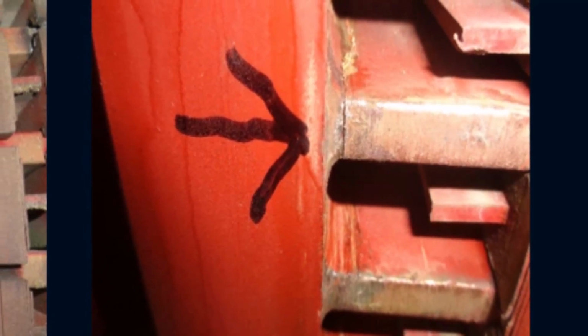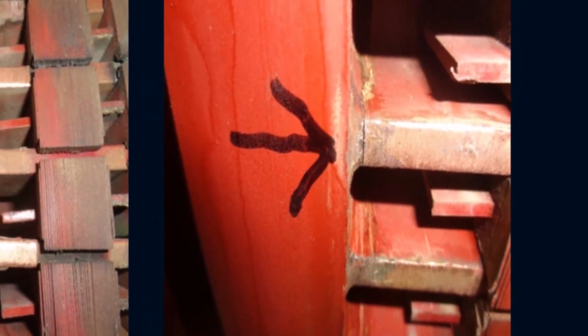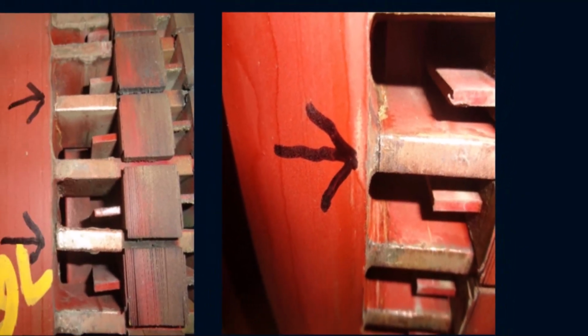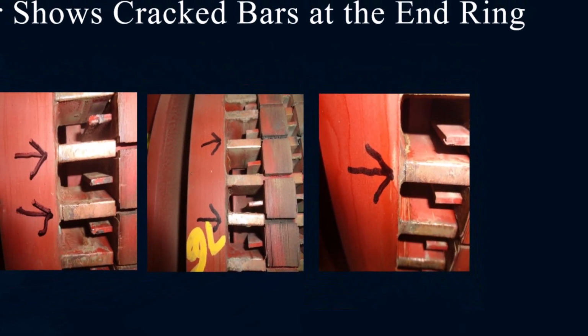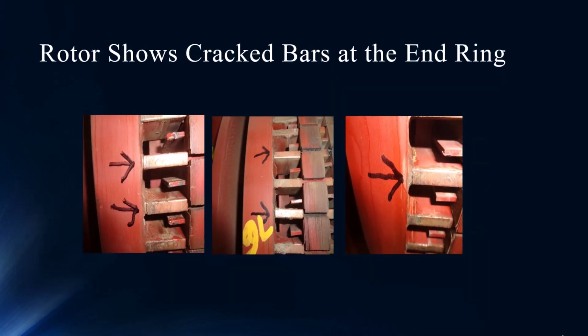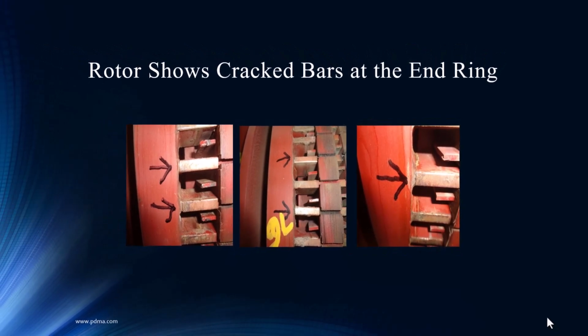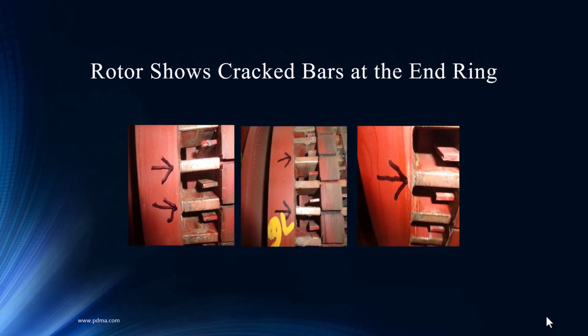So this rotor was caught early enough that it can be repaired and put back in service. You see some heating on one of those bars by the lamination, maybe traveling along the side. Another thing I noticed in the middle picture, it says 76—that's how many bars are there. How many times do we tell our customers to develop a relationship with the motor shop? When you send motors in for bearings or whatever, have them pull that rotor if you don't know the number of rotor bars, and just count them.